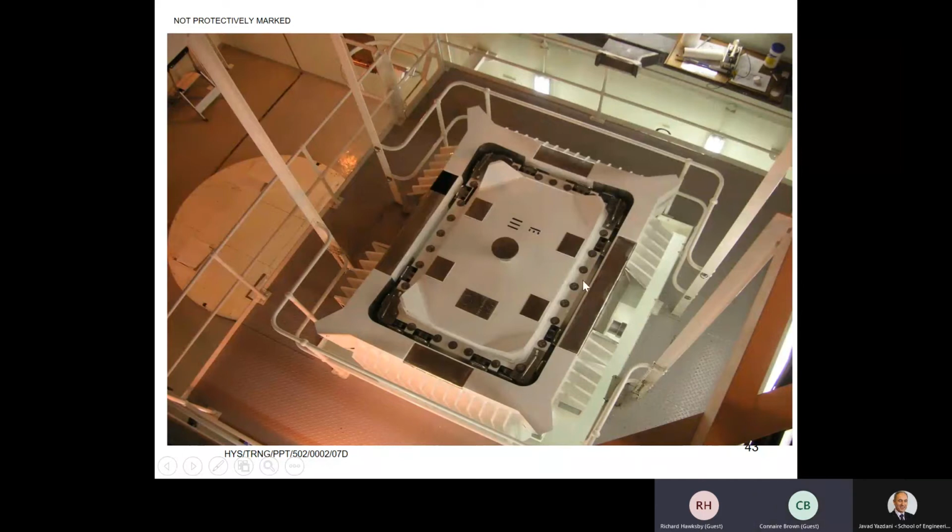So although there are bolts around holding the lid in, the lid is actually held in by wedges, chocks, cheese-shaped. They've got little handles on them, and there's a double wedge arrangement. Very clever design, in that it doesn't rely on the bolts holding the lid on. It relies on these wedges that are put in. Obviously, if you have a door wedge, it's harder to pull the lid off with a wedge in. The more it digs in, the more it won't come off. The bolts are really just to compress the seal that keeps the fluid inside the flask. Very clever, to reduce the reliance on an operator torquing down the bolts to the right torque value. Well, it's part of the integrity claim, so it keeps the fluid in, but in terms of keeping the lid on, it's kept on by chocks.